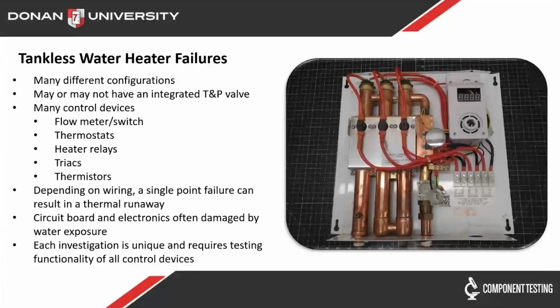So an example is, I was looking at a water heater where the flow switch failed in a state that would lead the water heater to believe that the water was still flowing when it clearly wasn't. So as soon as the water heater was energized, the heaters came on. Now, what was interesting about this one was it didn't result in a failure of the water heater, but it did burst PEX that was located downstream of the water heater. And so the failure may not be immediately obvious that it was the water heater.